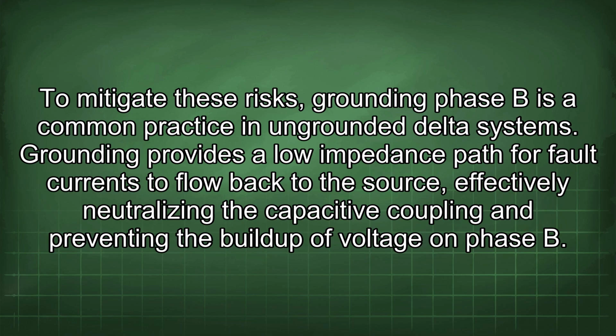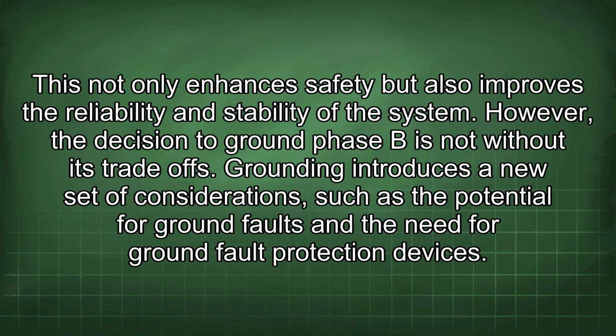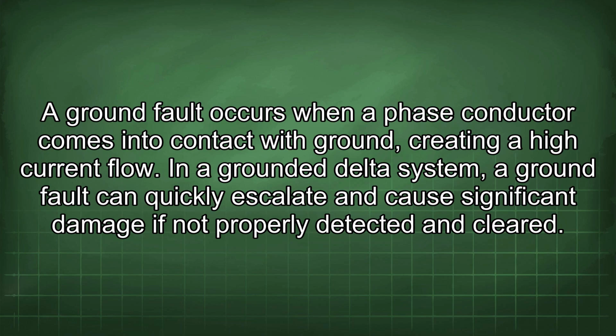Grounding provides a low impedance path for fault currents to flow back to the source, effectively neutralizing the capacitive coupling and preventing the buildup of voltage on phase B. This not only enhances safety but also improves the reliability and stability of the system. However, the decision to ground phase B is not without its trade-offs. Grounding introduces a new set of considerations, such as the potential for ground faults and the need for ground fault protection devices. A ground fault occurs when a phase conductor comes into contact with ground, creating a high current flow. In a grounded delta system, a ground fault can quickly escalate and cause significant damage if not properly detected and cleared.